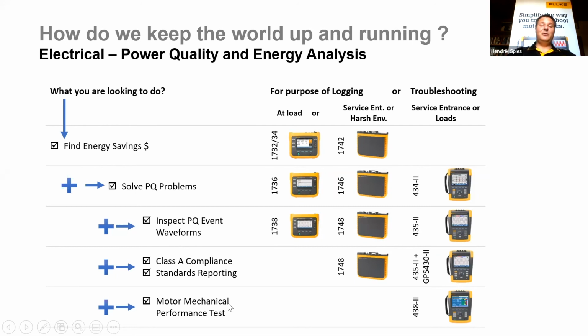And something that's quite unique with Fluke is we've got the Fluke 438, which actually does energy loss calculator based on your active, reactive power, line losses, voltage imbalance, and neutral losses. But this unit as well, based on the nameplate of the actual motor, remember the motor is electromechanical. Based on the electrical nameplate, we can also do mechanical measurements as well without disconnecting the motor. So we can do torque-based measurements with the unit as well. Very popular with industrial customers with quite a lot of motors that they use in the field.